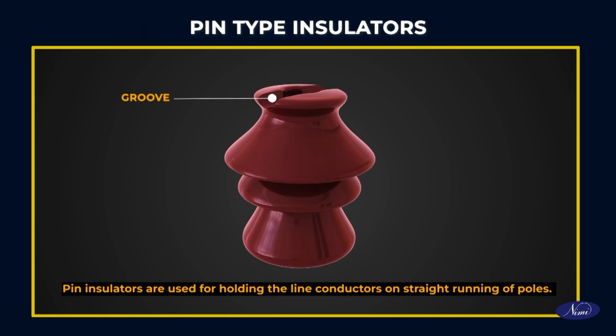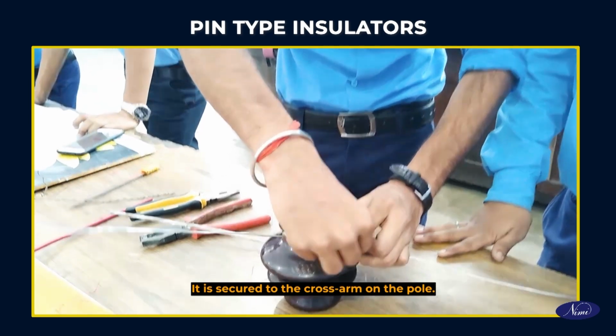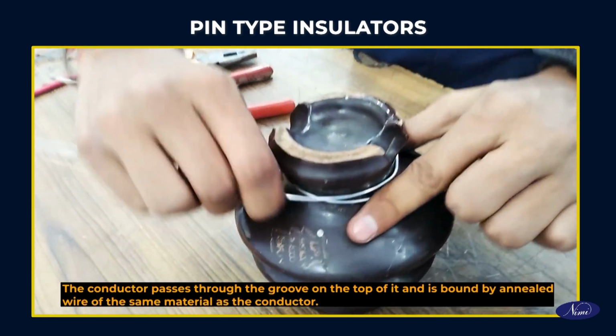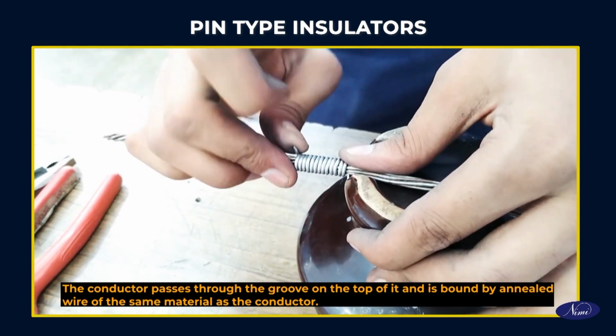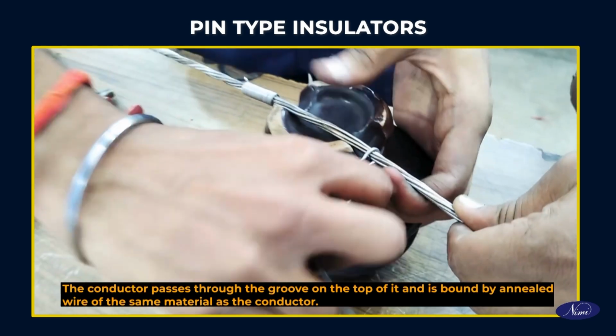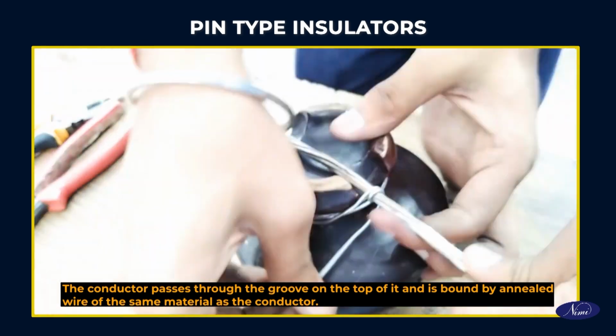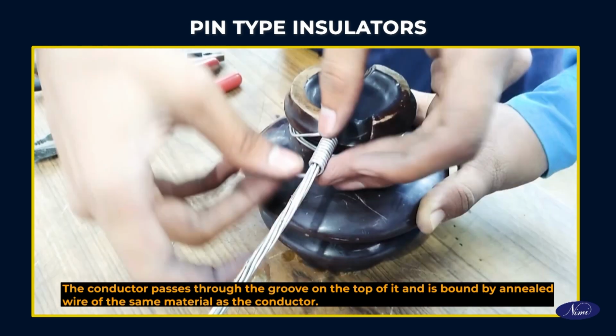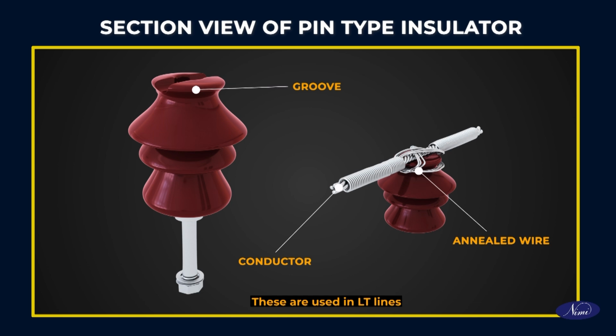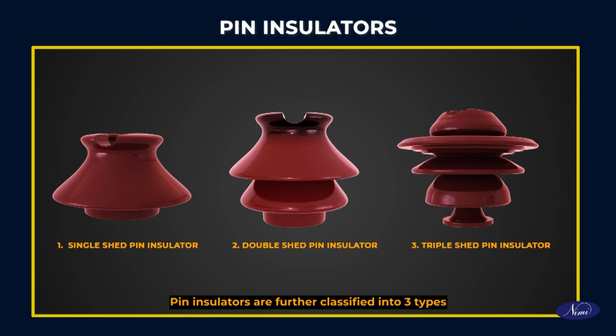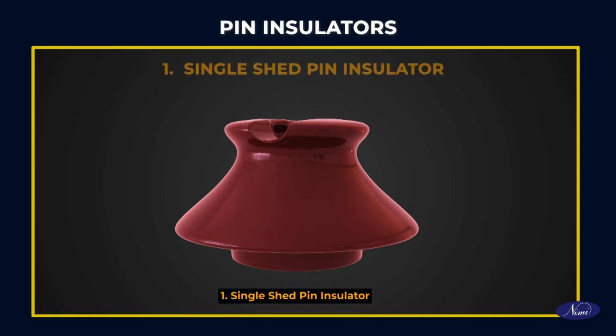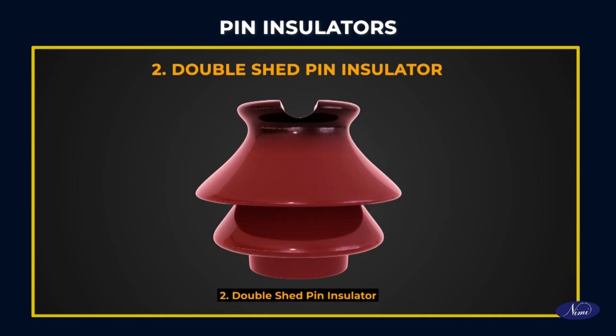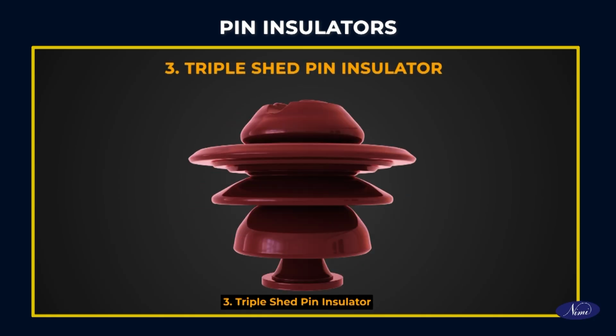Pin insulator. Pin insulators are used for holding the line conductors on straight running of poles. It is secured to the cross arm on the pole. The conductor passes through the groove on the top of it and is bound by annealed wire of the same material as the conductor. These are used in LT lines. Pin insulators are further classified into 3 types: single shed pin insulator, double shed pin insulator, triple shed pin insulator.